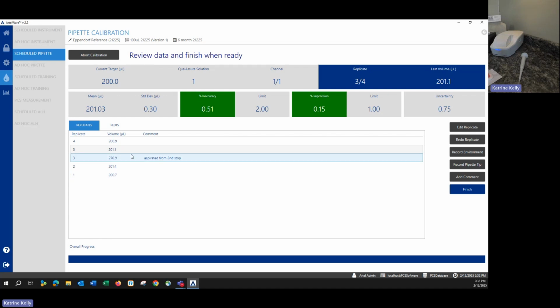And so then next it will recalculate, removing that data point that I over-aspirated from, and just base statistics on the four good samples. You can see it's gone back to green. I'm within my tolerance limits for my inaccuracy and imprecision. If I did have the calibration plan set up to do another volume, there would be a button down here to the right that would say next volume, and you would click next volume.